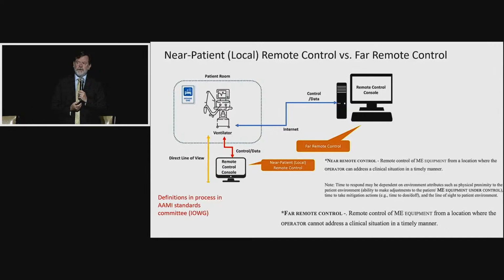The quality of information you see might matter greatly. How much information do you need to bump up FiO2 on a ventilator? Maybe not a lot, at least if it's transient until you get to the bedside. But maybe if you're going to adjust the trigger pressure on a ventilator or the timing to deal with asynchrony, you're probably not going to be willing to do that unless you can see the patient, see vital signs, and see real-time ventilator waveforms. It doesn't mean you can't do it remotely, but you might need more information - it might have to be real-time.